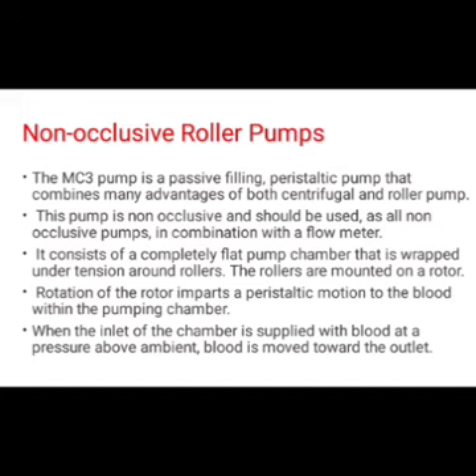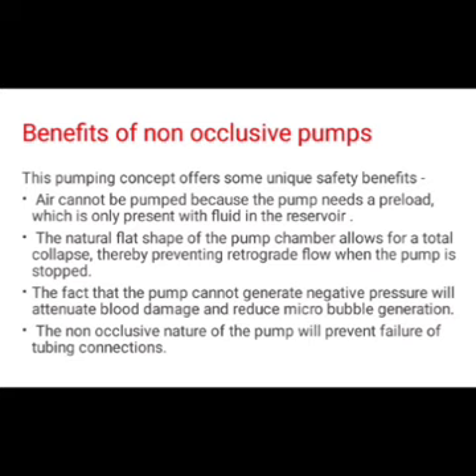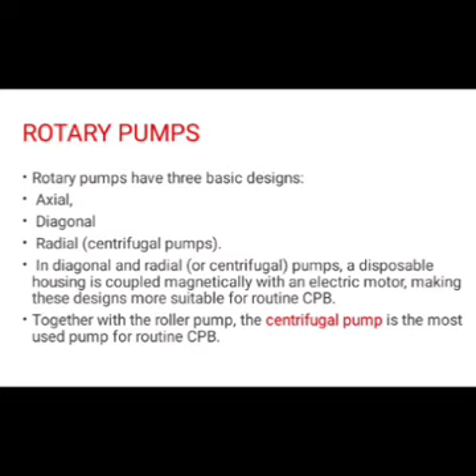Benefits of non-occlusive pumps. This pumping concept offers some unique safety benefits. Air cannot be pumped because the pump needs a preload, which is only present with fluid in the reservoir. The natural flat shape of the pump chamber allows for a total collapse, thereby preventing retrograde flow when the pump is stopped. The fact that the pump cannot generate negative pressure will attenuate blood damage and reduce microbubble generation. The non-occlusive nature of the pump will prevent failure of tubing connections.